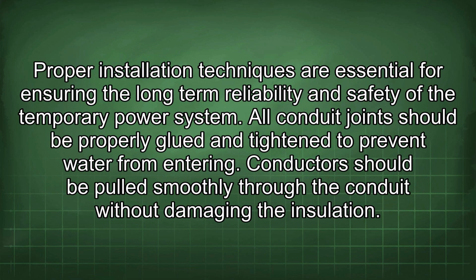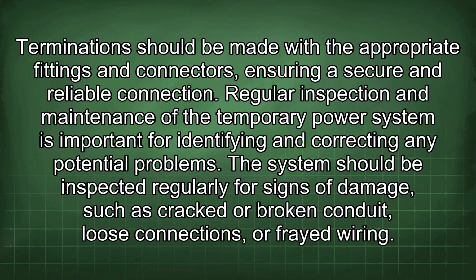Proper installation techniques are essential for ensuring the long-term reliability and safety of the temporary power system. All conduit joints should be properly glued and tightened to prevent water from entering. Conductors should be pulled smoothly through the conduit without damaging the insulation. Terminations should be made with the appropriate fittings and connectors, ensuring a secure and reliable connection.